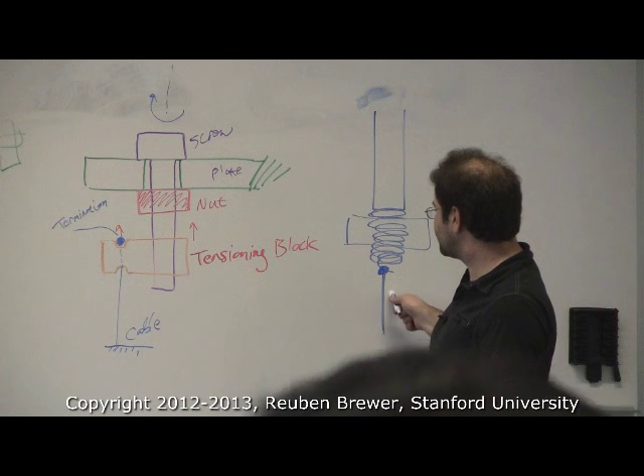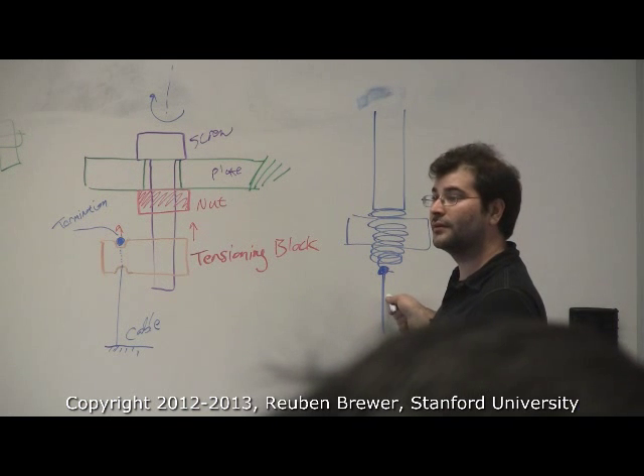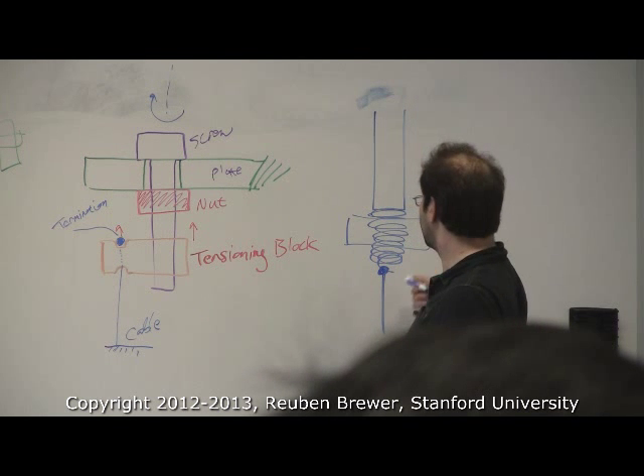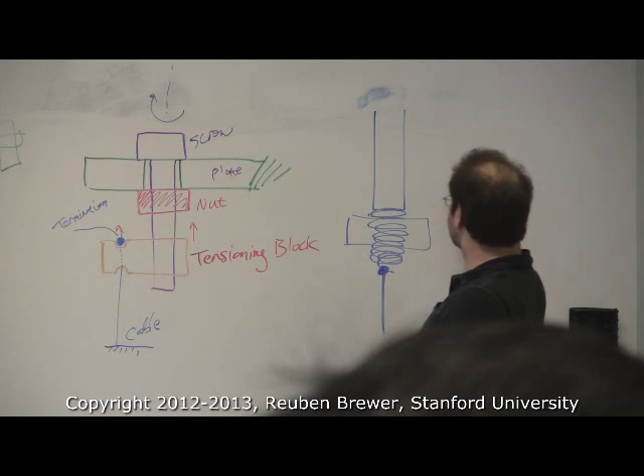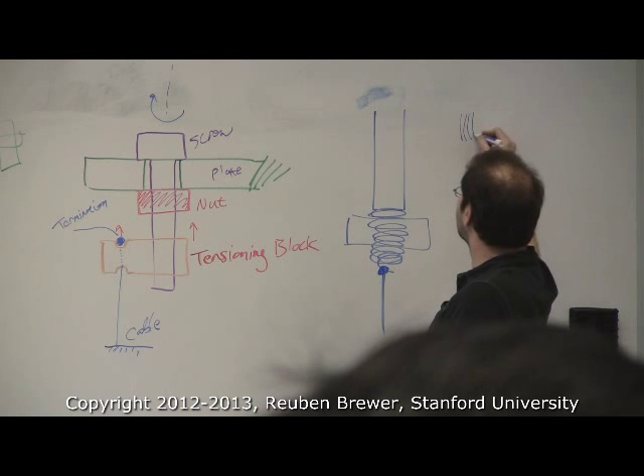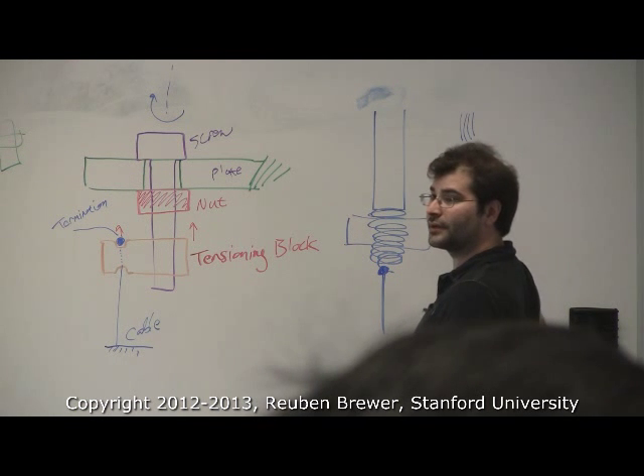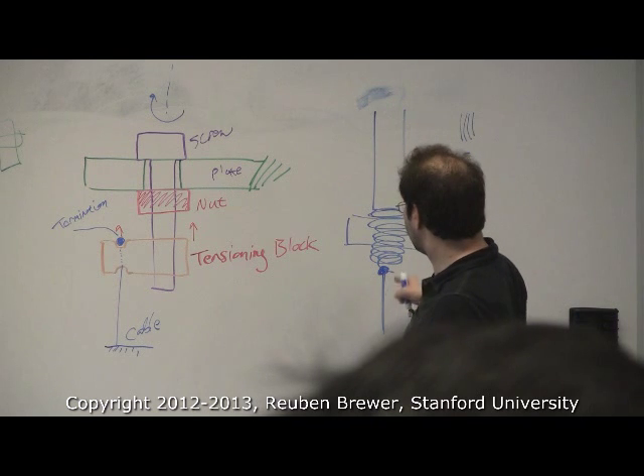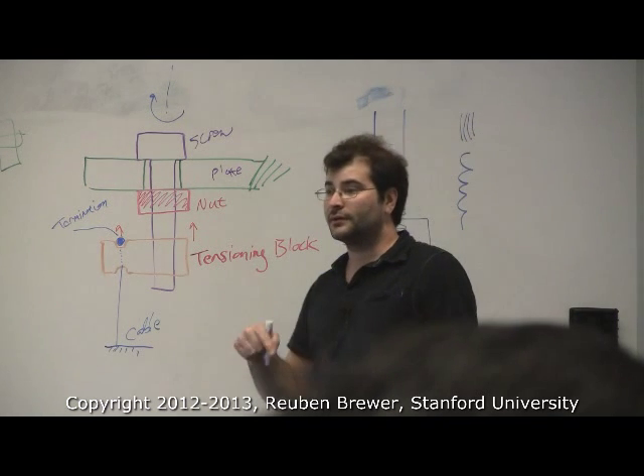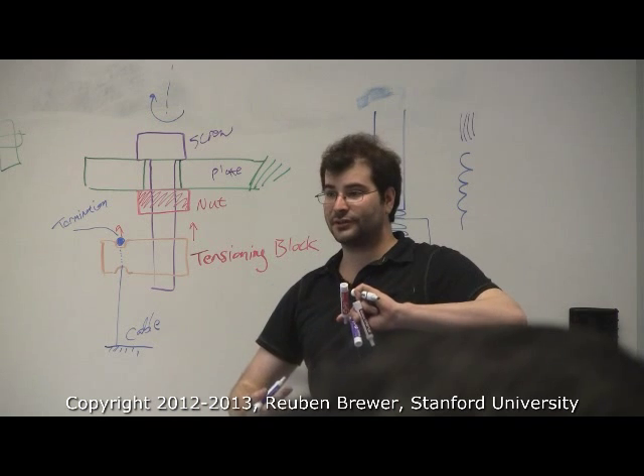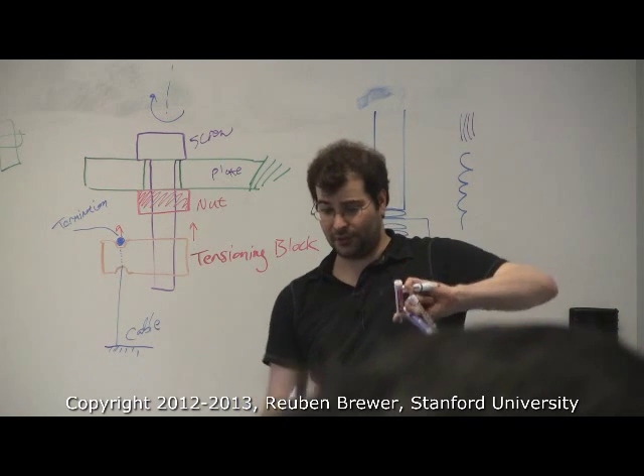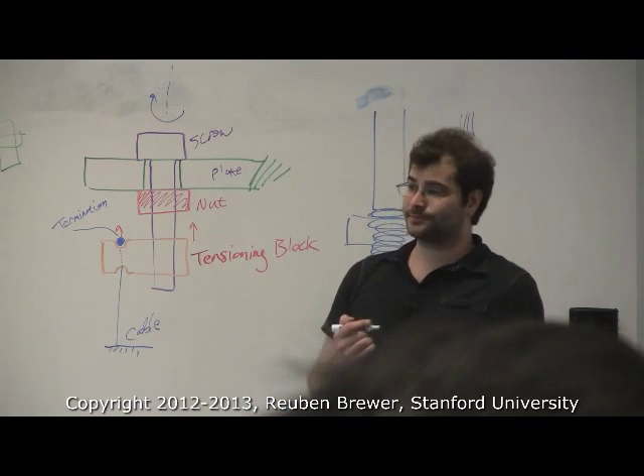The main reason for this is, remember, this isn't a single strand. This is made up of anywhere from 7 to 49 strands. They take the strands like this, a bunch of them, and twist them around each other, so it's like yarn in a spiral. If you put it on a screw and rotate it, you're either crunching the fibers against each other and ruining the cable, or undoing the helix and still ruining the cable.